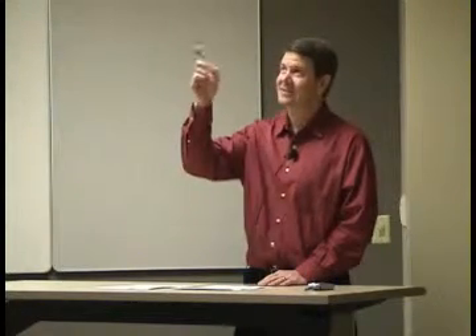VAVs, the noise level between a minimum and maximum set point can be really pronounced. You can really hear that air screaming through the registers, depending on what type of diffusers they used and how much they're trying to dump out of every one.